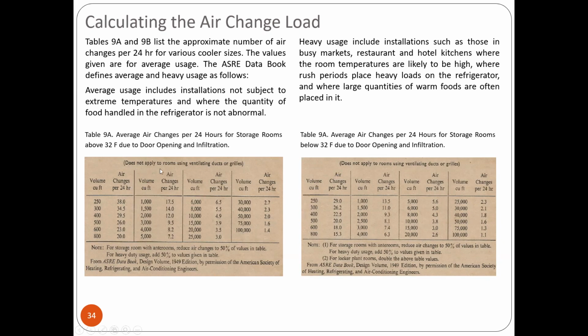So note that this does not apply to rooms using ventilating ducts or grills. So volume, air changes, and 250 cubic feet to 100,000 cubic feet. Ito naman, 252, ganun din. Okay. Yan yung mga value. May mga notes. For storage room with anteroom, reduce air changes 50% of the value on the table. For heavy usage, add 50% to the values given in the table. So yan. Okay.